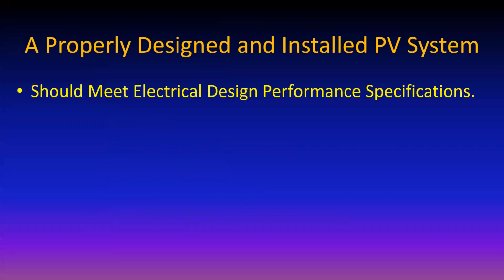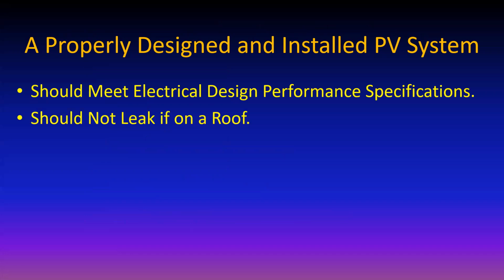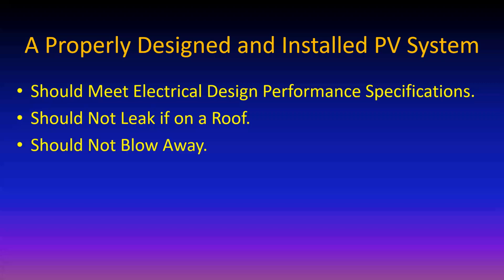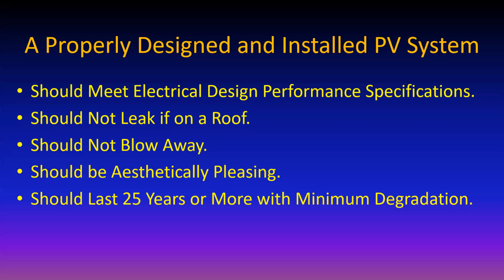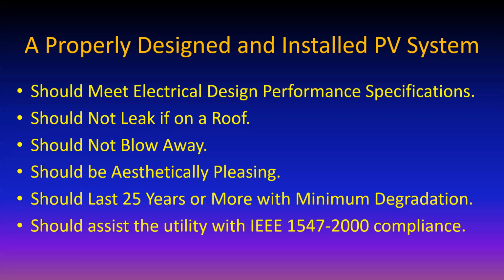So what should you expect from a properly designed installed PV system? Well, first of all, it has to meet all the electrical design and performance specs. And that's fairly straightforward to check and prove after a month or so of operation. It shouldn't leak if it's on a roof, pretty obvious. It shouldn't blow away, that's also pretty obvious. It should be aesthetically pleasing, should last 25 years or more, and it should make the utility happy by complying with IEEE 1547-2000, because that's a way that PV owners actually help the utility. And what could be better than a partnership with the electric utilities where everybody wins?